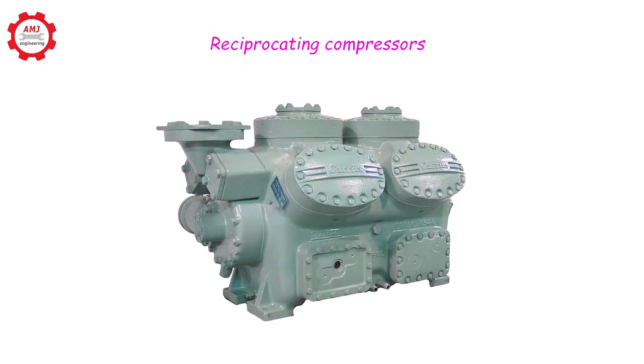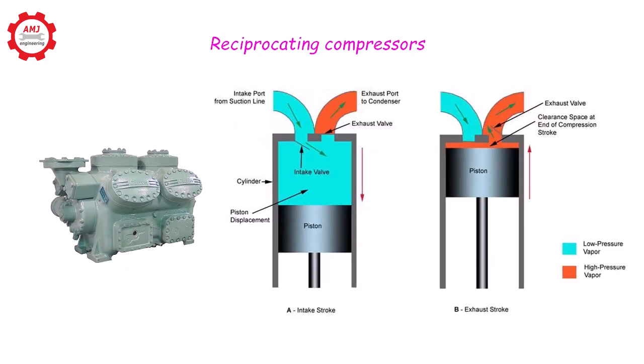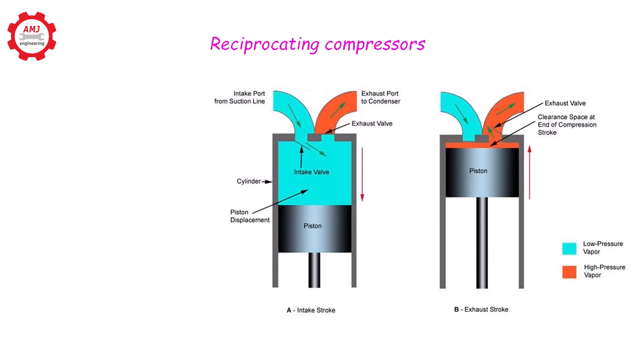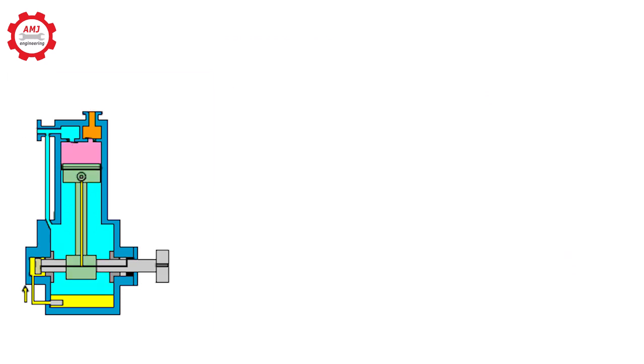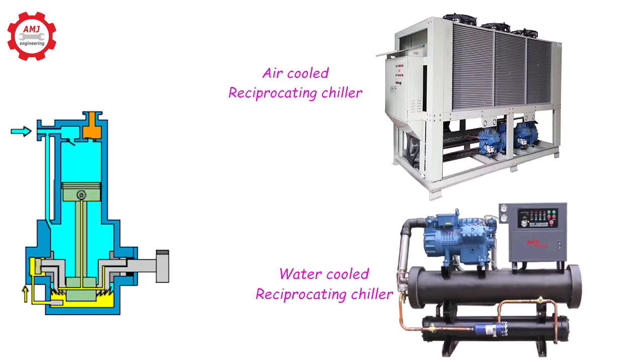Reciprocating compressors operate similar to a car engine; they use a piston driven from a crankshaft. The refrigerant is drawn into the cylinder during the downstroke and compressed in the upstroke. These compressors could be found on air-cooled and water-cooled chillers up to 200 tons of refrigeration.